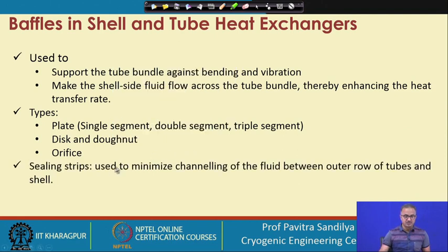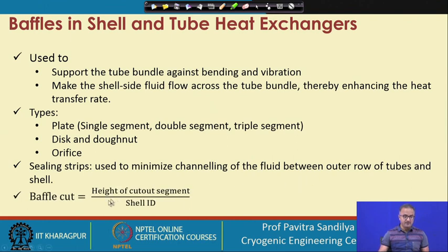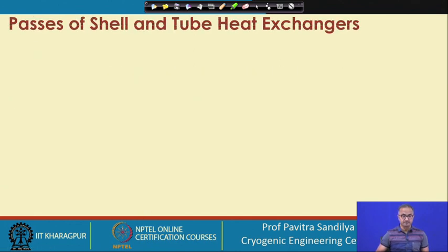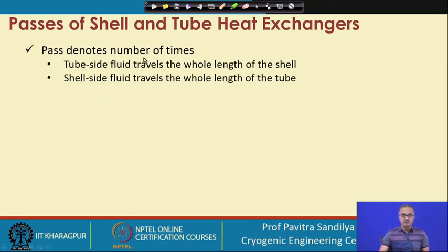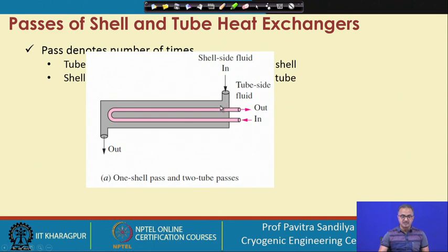Sealing strips are used to minimize channeling of fluid between the outer row of tubes and the shell. Baffle cut is defined as the height of the cutout segment to the shell inner diameter. A pass denotes the number of times tube side fluid or shell side fluid travels the whole length of the shell or tube. In a configuration with one shell pass and two tube passes, the shell side fluid travels once while the tube side fluid traverses the length twice.